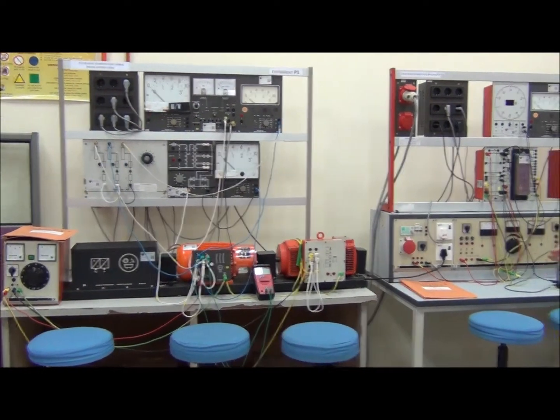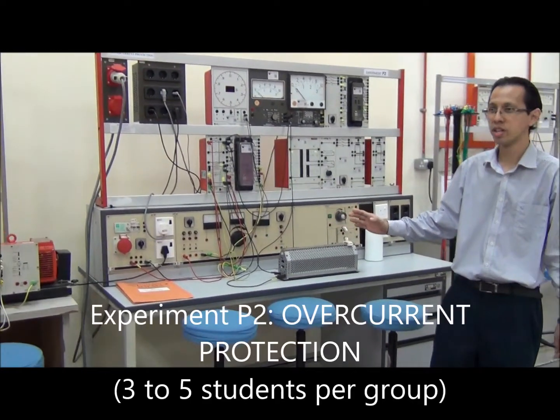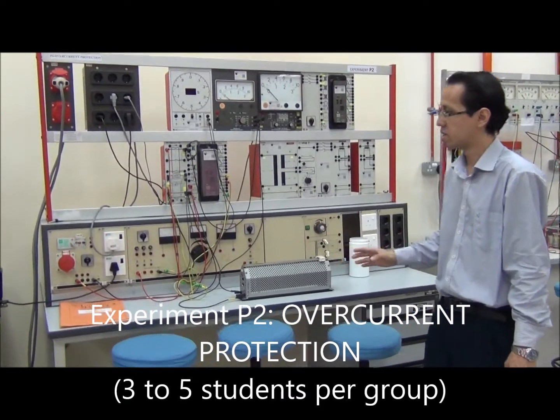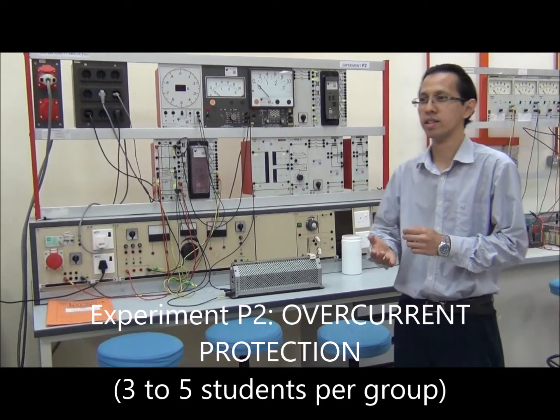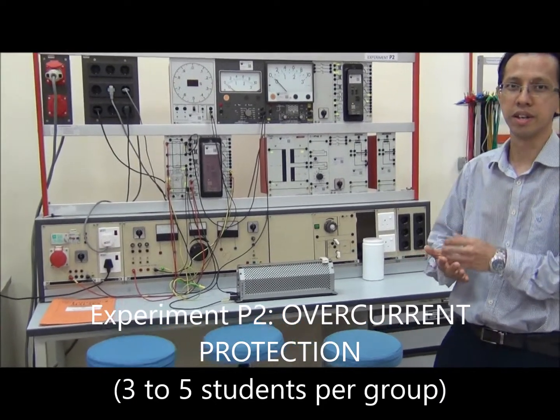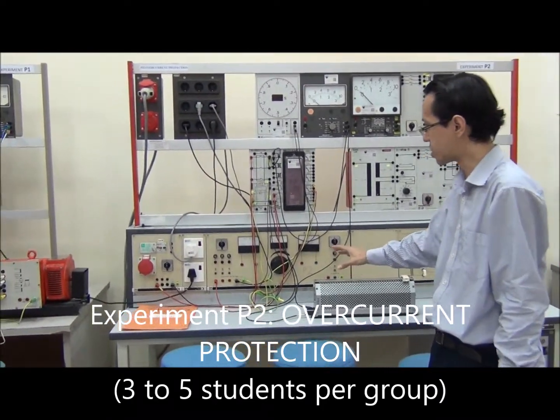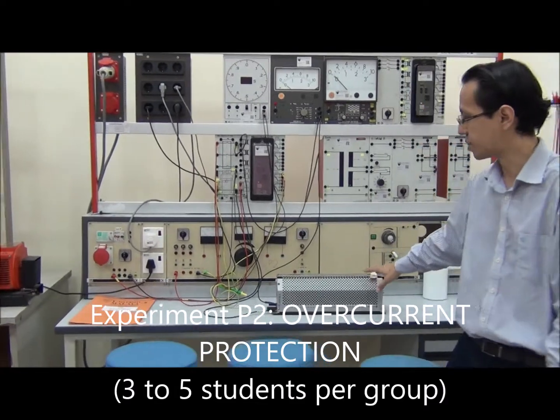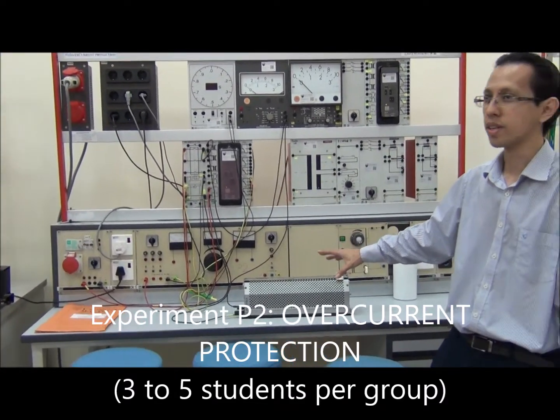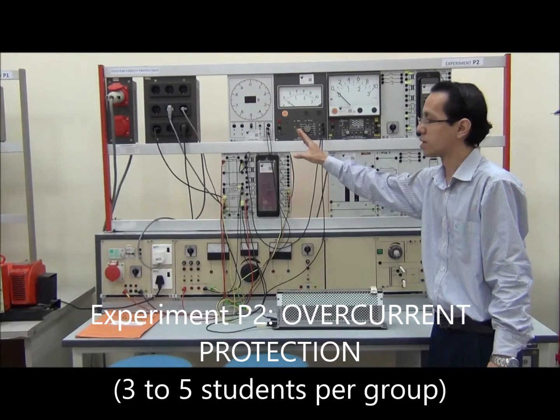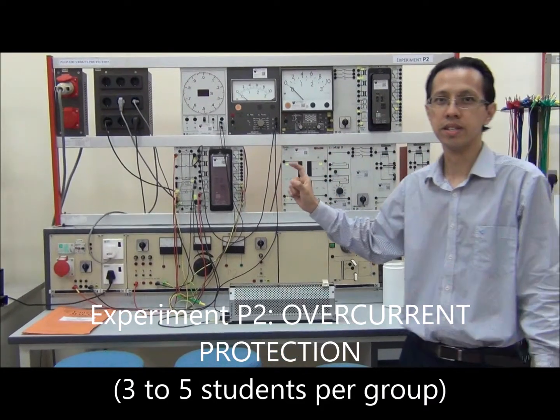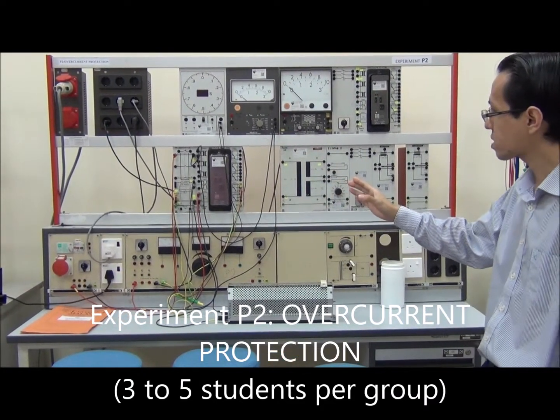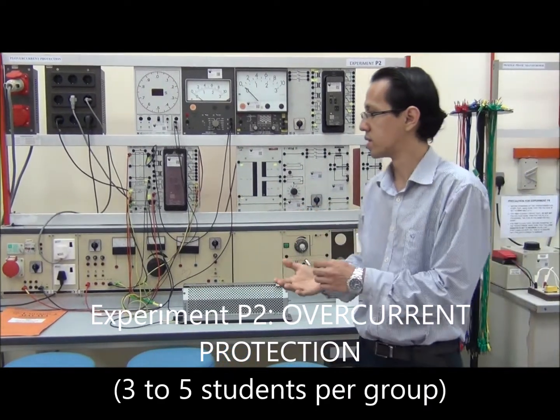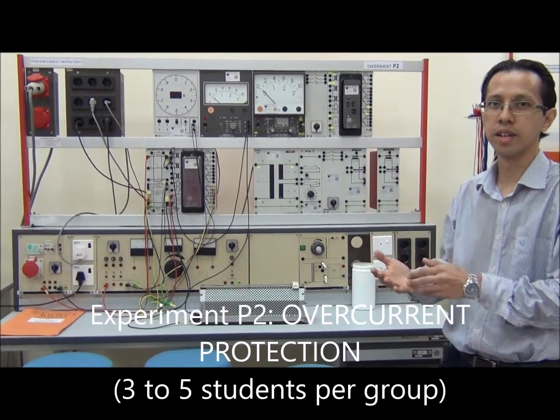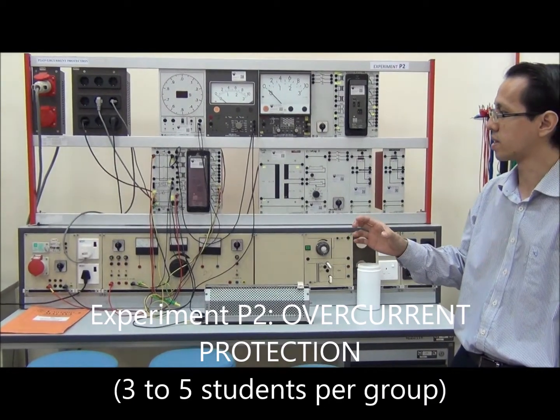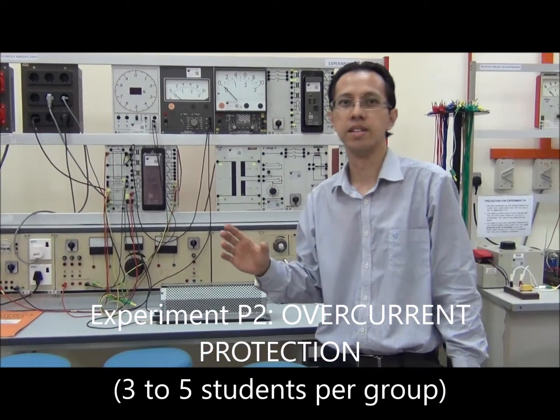The next experiment is about overcurrent protection. It's about identifying the characteristics of the overcurrent relay, where students have to change the power supply or the resistance of the load, and they need to record the tripping time of the relay. Once they have obtained the results, they will plot the curve, and that curve shows the characteristics of the relay.